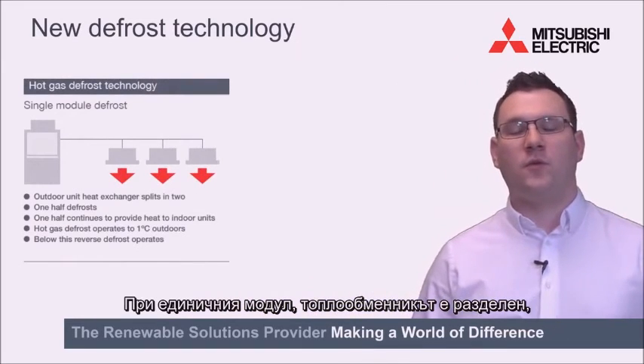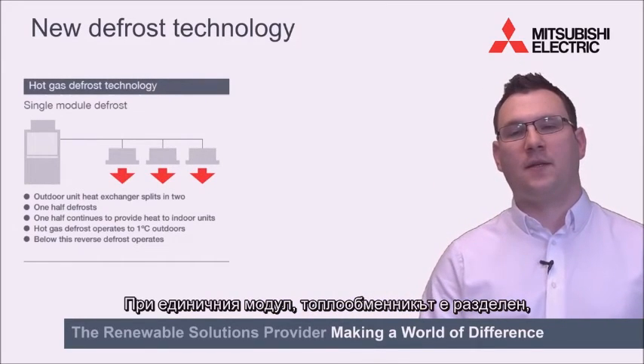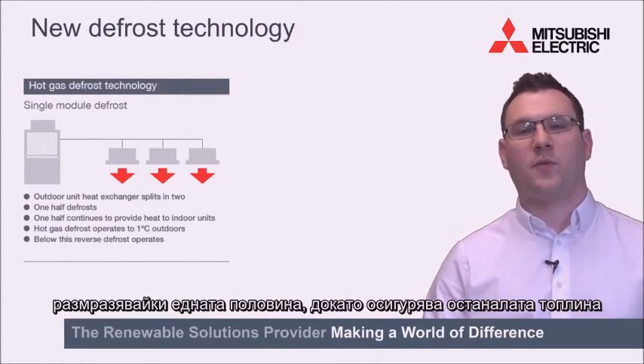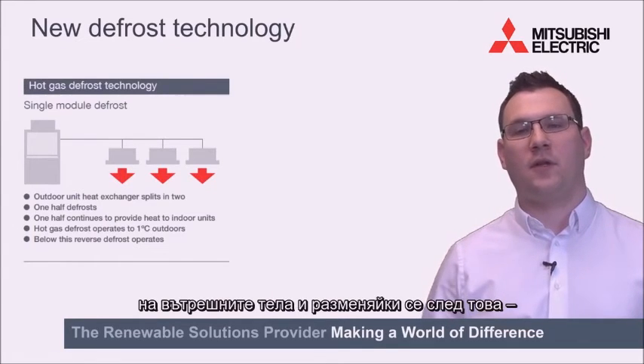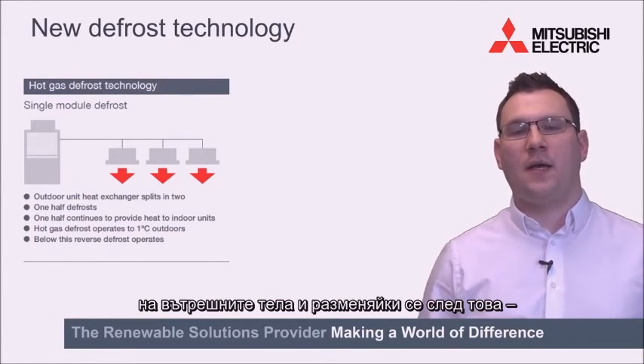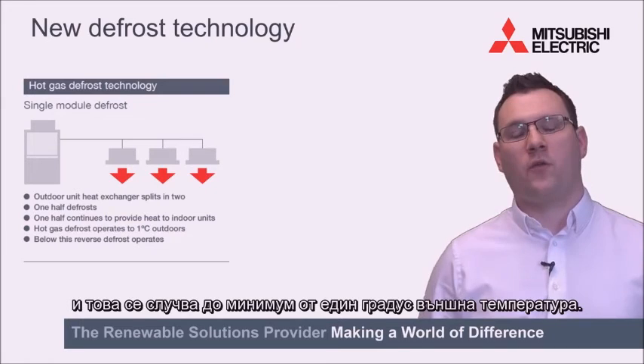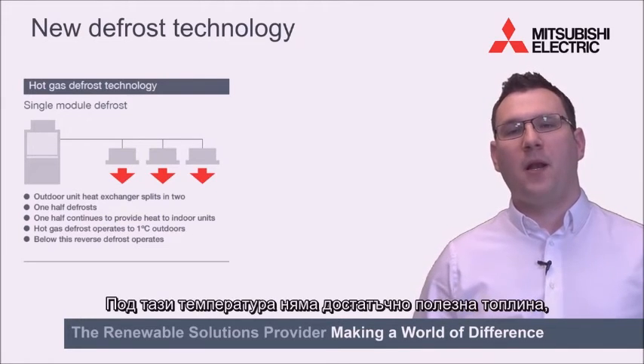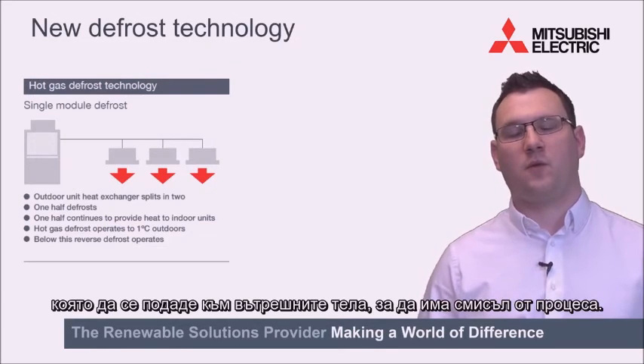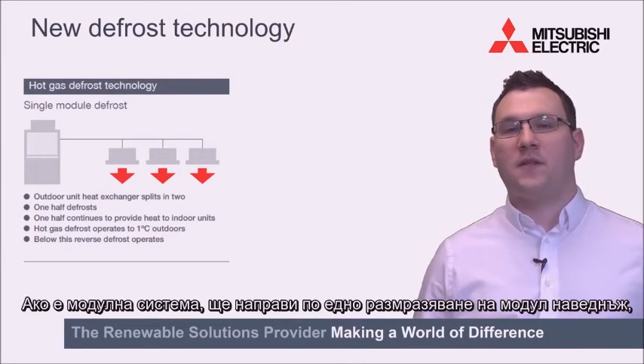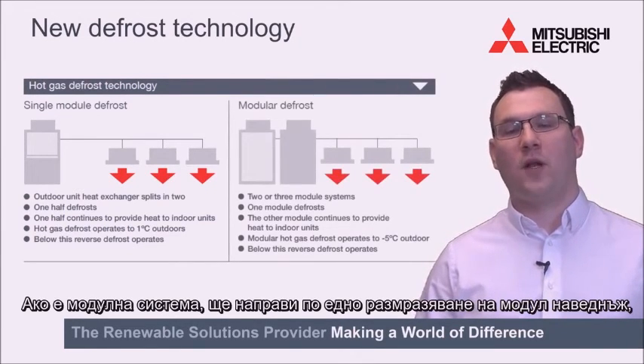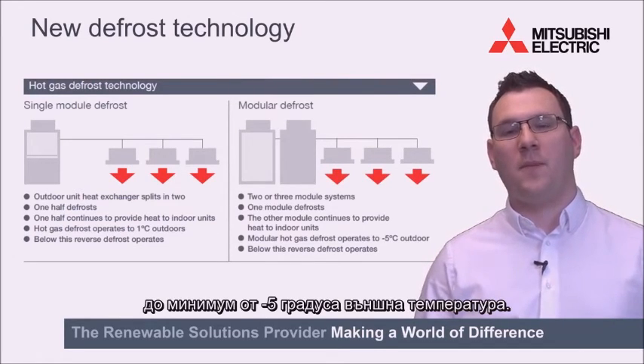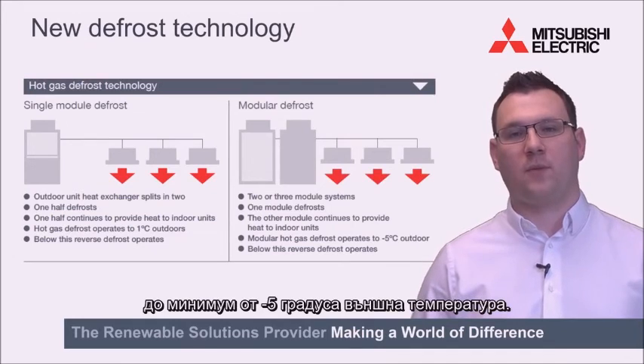In a single module, the heat exchanger is split, defrosting one half whilst providing the other heat to the indoor units, and then rotating, and it will do this down to a minimum of 1 degree outdoor temperature. Below this, there's not enough meaningful heat to give to the indoor units to make it worthwhile. If it's a modular system, it will do one defrost module at a time, and it will do this down to a minimum of -5 degree outdoor temperature.